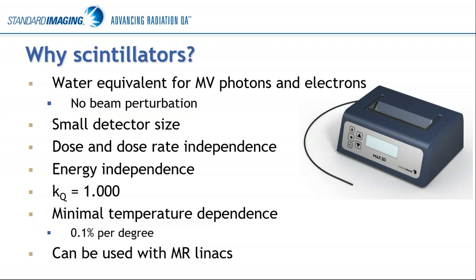The detectors can be made quite small. They are dose and dose rate independent. We don't see energy dependence with them. The KQ factor, from a number of publications as well as measurement, is shown to be unity, which is a huge advantage for these really small fields. There is a tiny bit of temperature dependence — about a tenth of a percent per degree — but this really doesn't matter if you're only doing QA measurements at room temperature. We are not FDA cleared for on-patient measurements yet, so usually this doesn't affect your QA measurements.